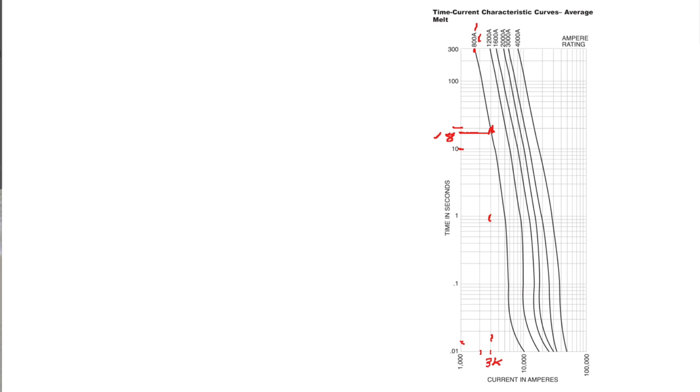Let's look at a second example. If we have the same 800 amp fuse but this time we apply 6,000 amps fault current, we follow the line up until it intersects with the 800 amp line, and it intersects right around here at 0.035 seconds.